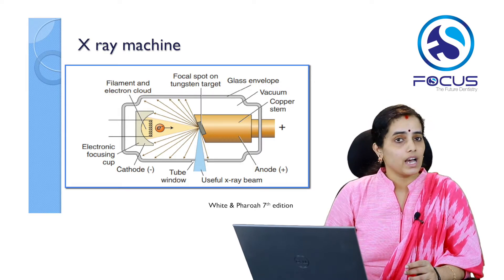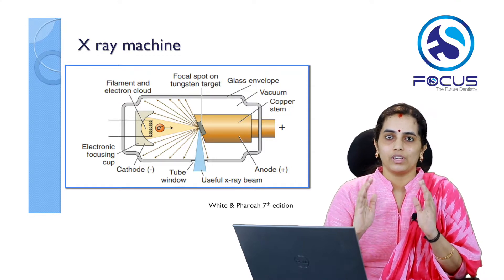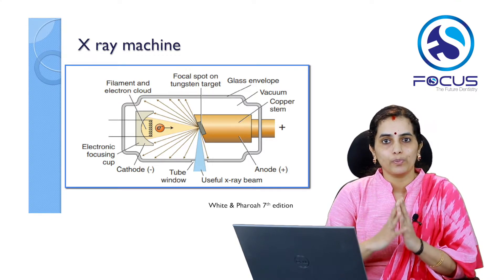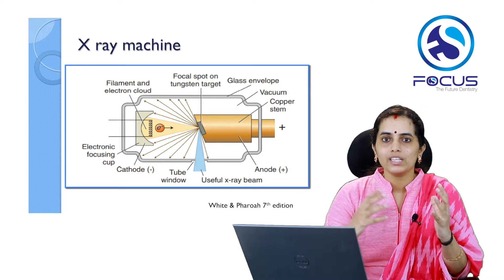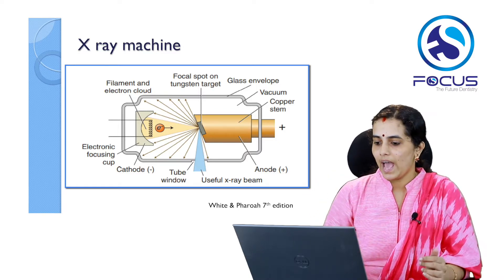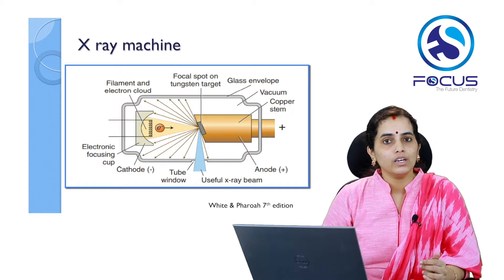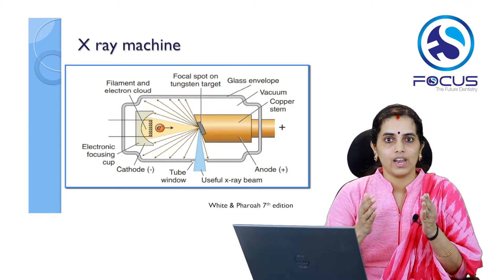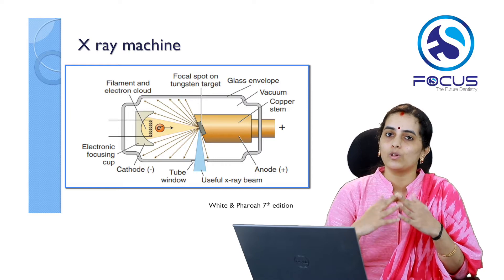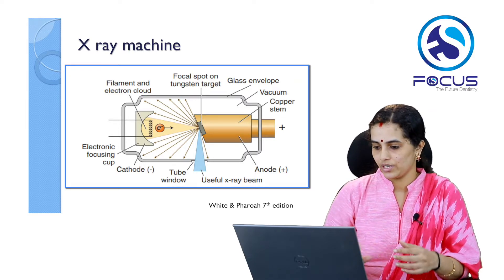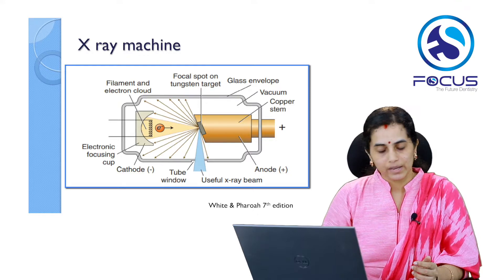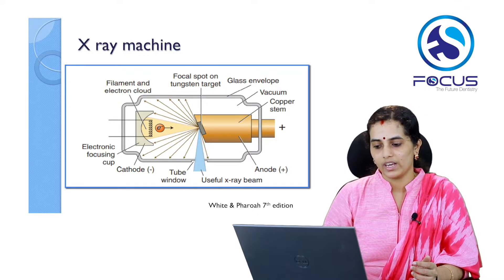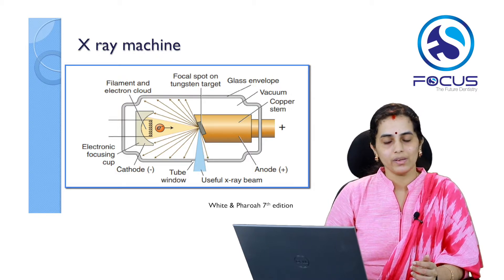Within the glass envelope, a vacuum is maintained to prevent collision of the fast-moving electrons with air and to prevent burnout damage of the tungsten filament. Surrounding the glass envelope is insulating oil, which also acts as a layer of heat dissipation. The useful X-ray beam exits the X-ray tube via the tube window.